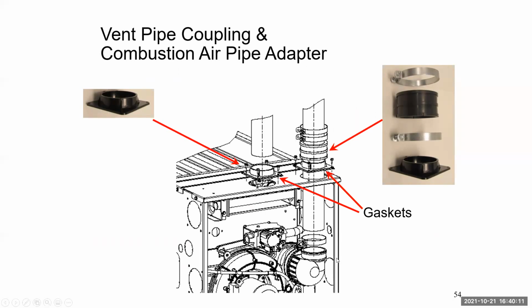Another part of not gluing this in is every now and then that rubber boot off your inducer motor is going to crack. It doesn't happen often, but it can happen. Or if you have to replace that inducer motor, it's not going with that new boot on there. So you're taking that off the old and putting on a new one. If everything's glued in up on top with that furnace, you're going to fight getting that inducer motor changed out. You're going to add about an hour to your service call, completely unnecessary. So use your rubber coupling and no glue.